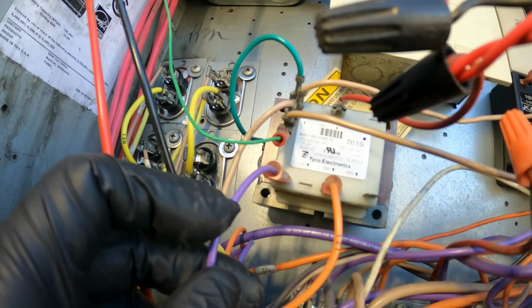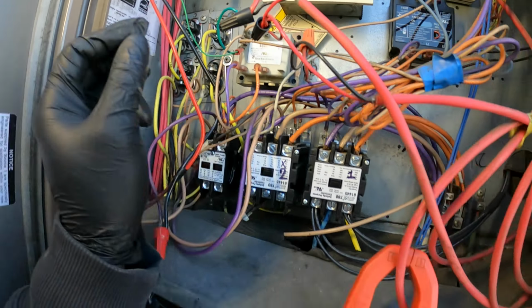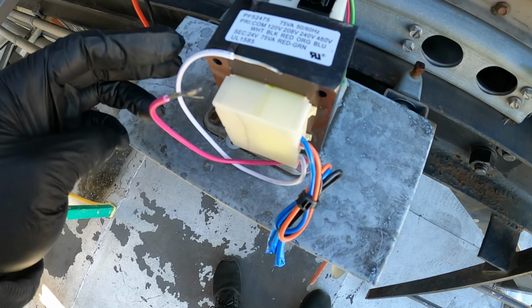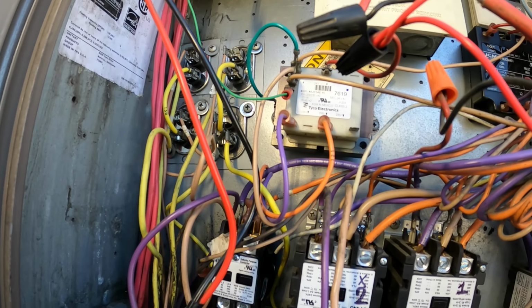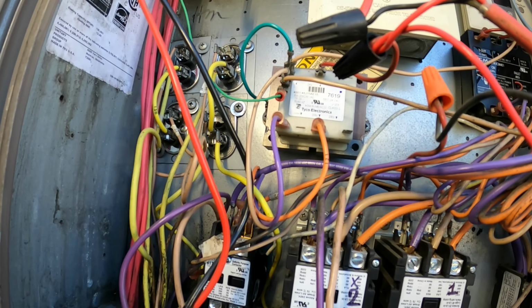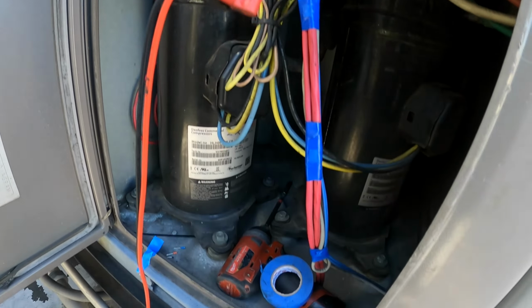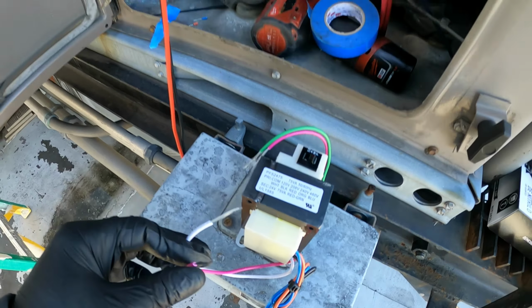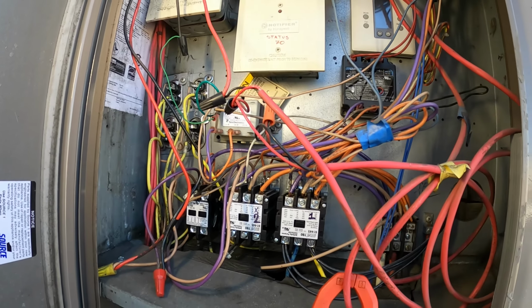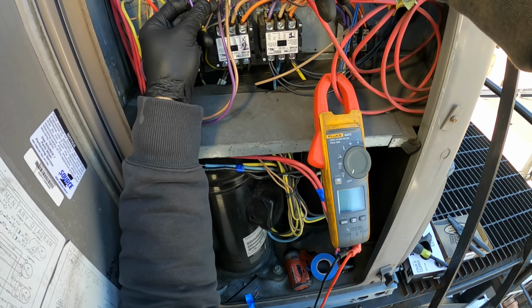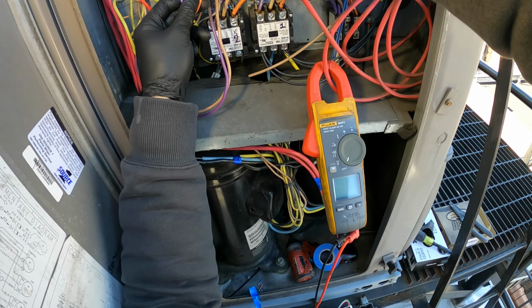This says the purple is our common and the orange is our 208. So white on this one, it's purple on there. White to purple, common to common, and then 208 to 208, so red and orange. I'm gonna show you how that's done, and we're just gonna go wire for wire. What I could do is cut the wire here at the edge where I can still see it.